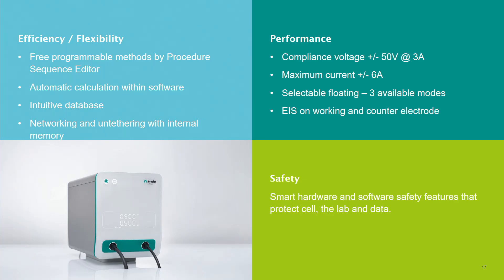In terms of performance, Vionic is a very powerful instrument and its high compliance voltage at high current is unique. If floating is needed, there are three modes the user can choose from, so grounding issues will not become a problem. Impedance measurements on both counter and working electrode are possible simultaneously, saving time when doing measurements in complete cell setups. Regarding safety, there are several software and hardware features to protect damage of electrodes and cells. Very useful is the internal memory of Vionic — even if the PC connection is lost, Vionic can store up to 10 million data points internally, which will be sent to the software after reconnecting the computer.